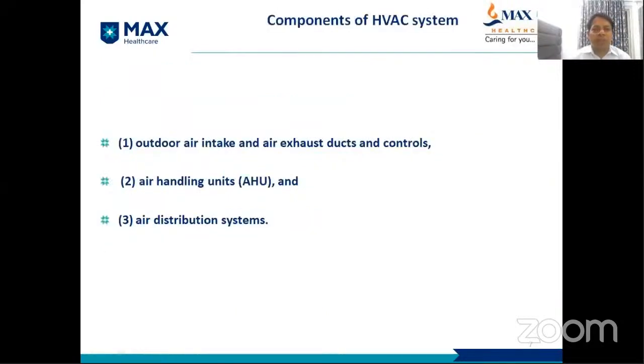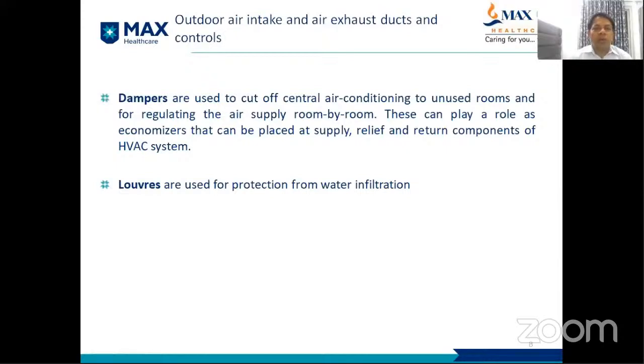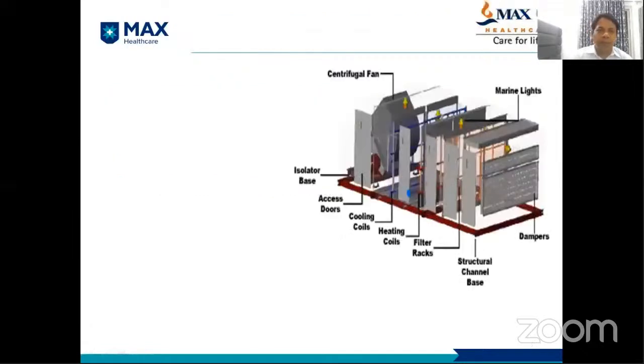The components of the HVAC system are, first, the outdoor air intake and air exhaust ducts and controls; second, the air handling unit, the AHU; and third, the air distribution systems. In the outdoor air intake and air exhaust ducts and controls, dampers are used to cut off central air conditioning to unused rooms and for regulating the air supply room by room. This can play a role as an economizer that can be placed at the supply, relief, and return components of the HVAC systems. Louvers are used for protection from water infiltration.